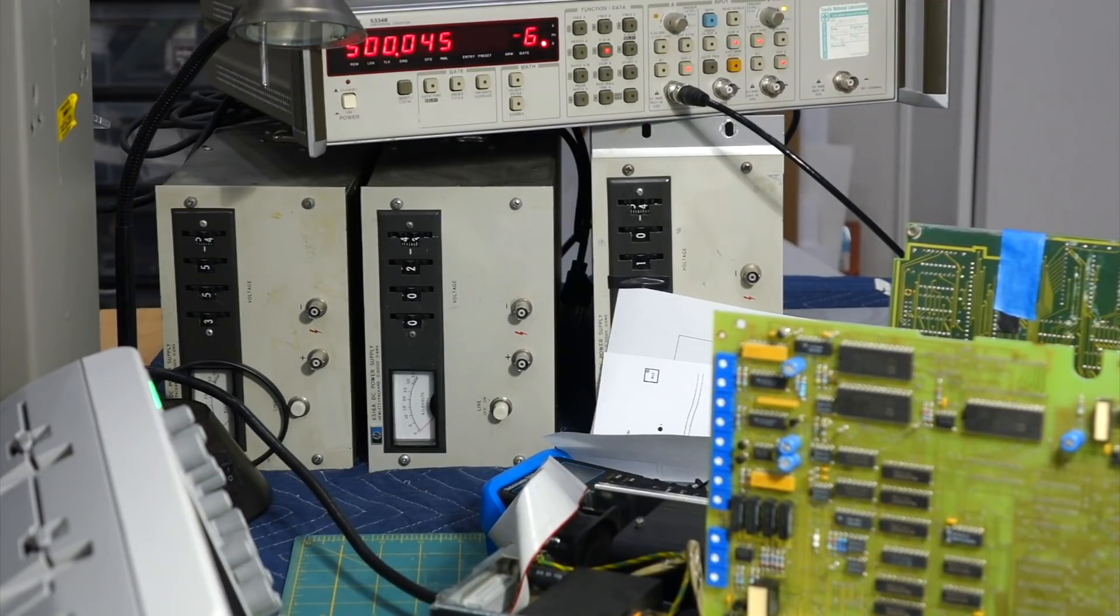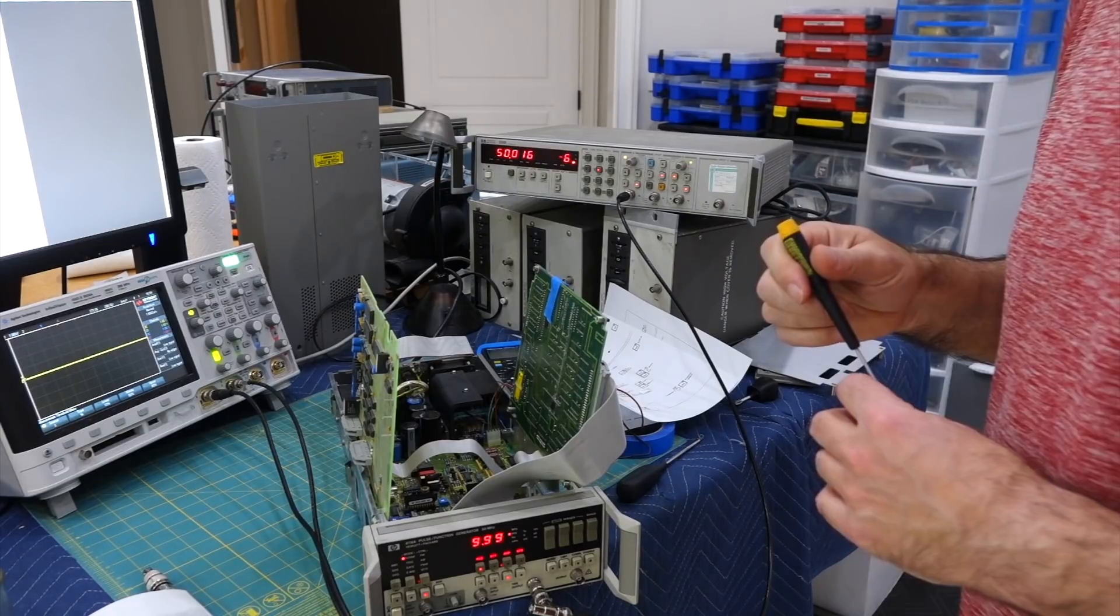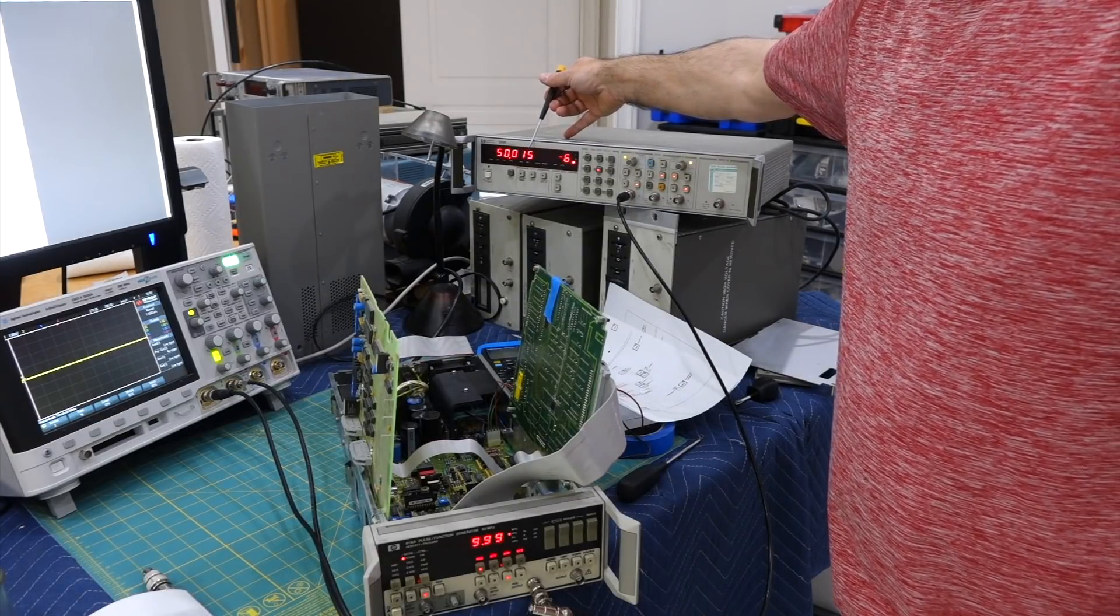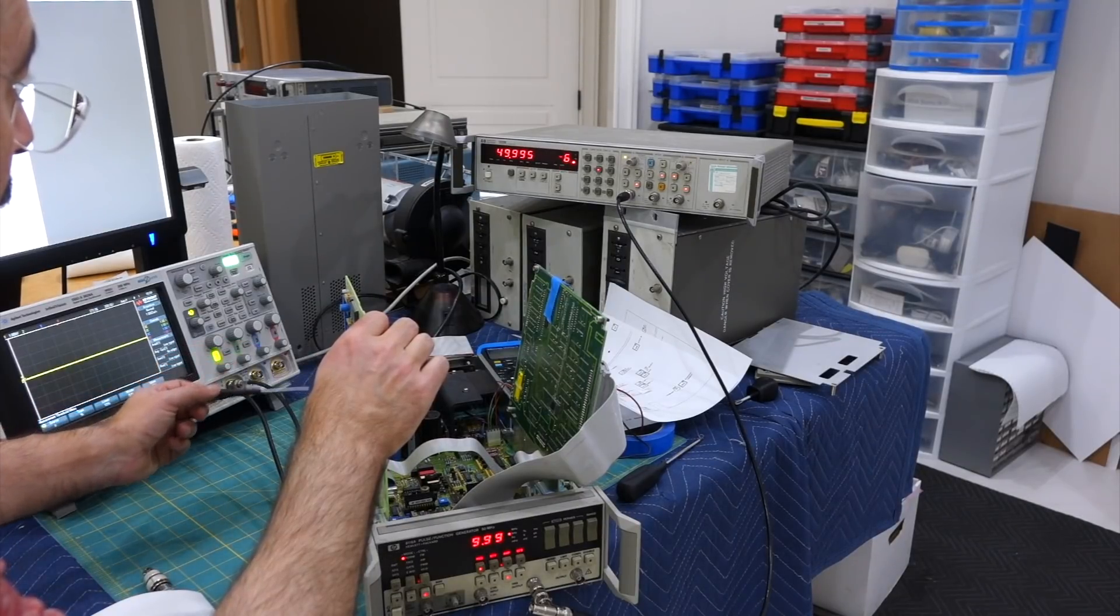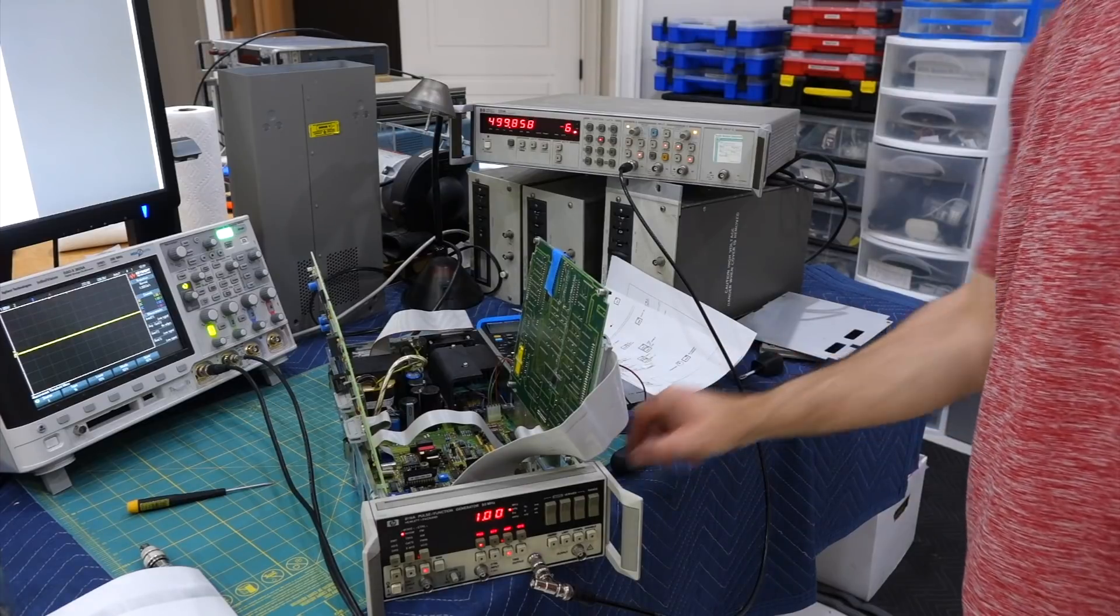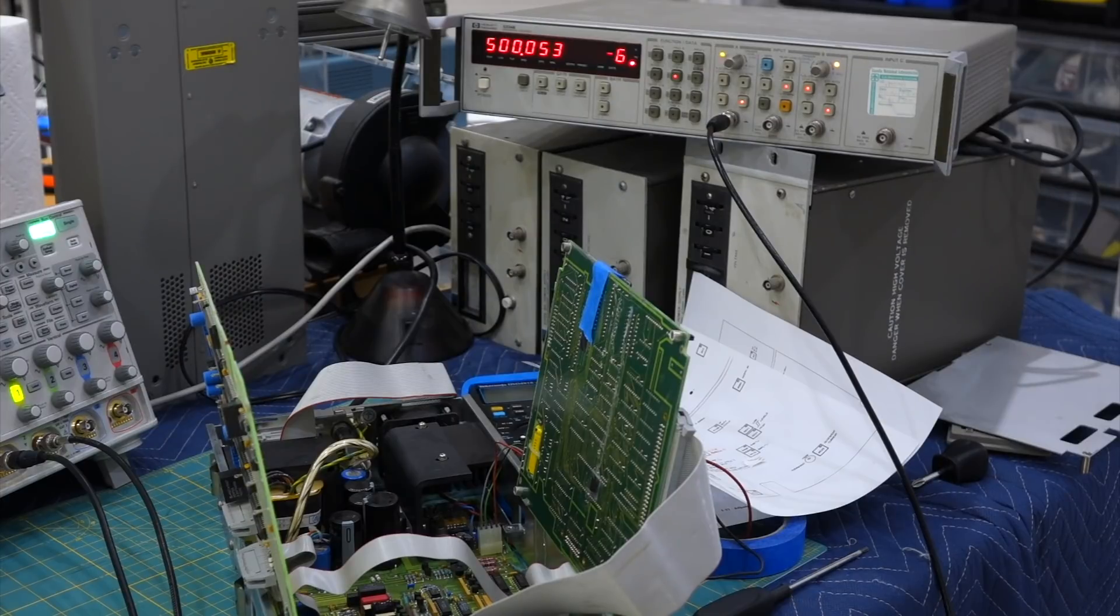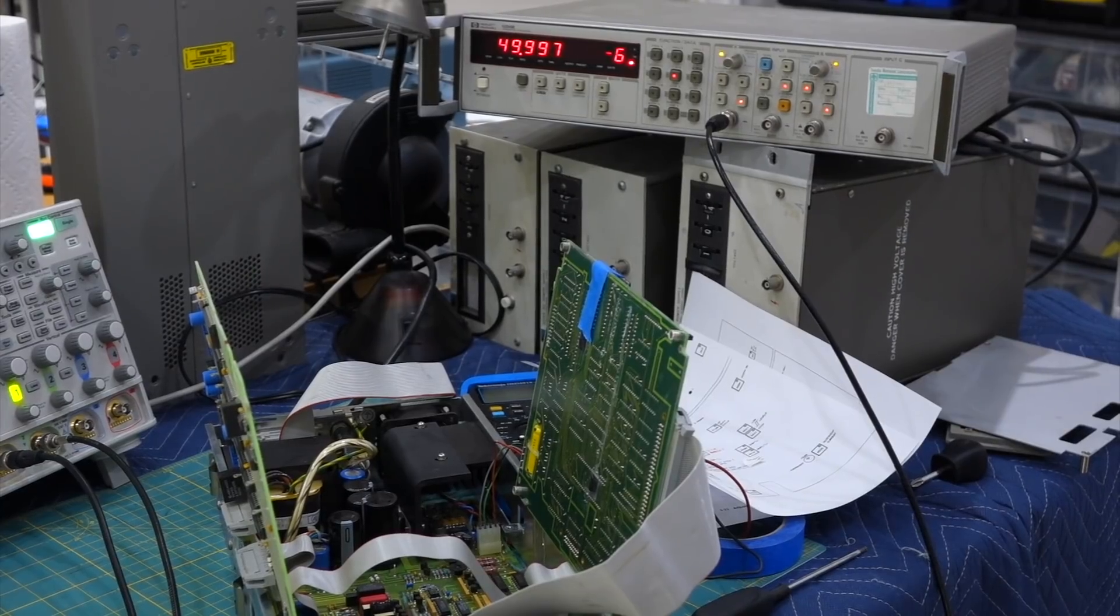So we have that adjusted. This is complicated. Next one, I have to go to 9.99 kHz. Why would you do that? I don't know. And I have to be 50 microseconds, plus minus 0.5. Looks like I am there. For once, something is correct. See if we can make it even better. Oh, that would be good. And then I have to go back to 1 kHz. Gee whee. And yeah, it has changed this one. So we have to go back and forth between the two. There we go. And now we go to 9.99. Oh, 50 microseconds. Exactly. So now we have both correct. Excellent.